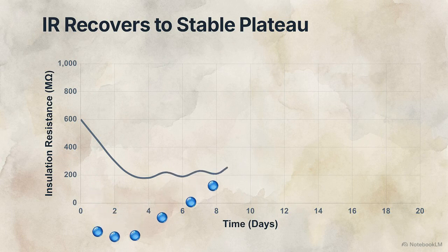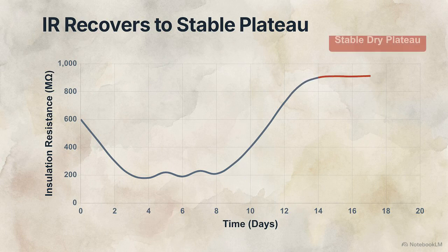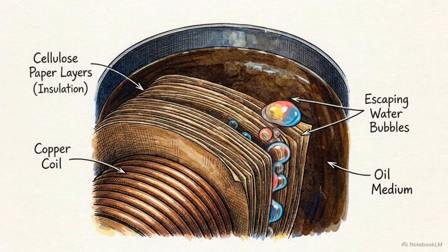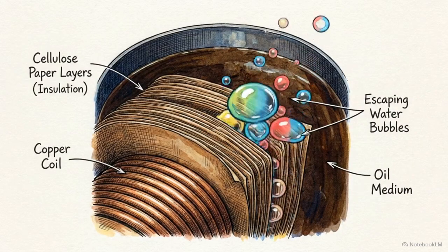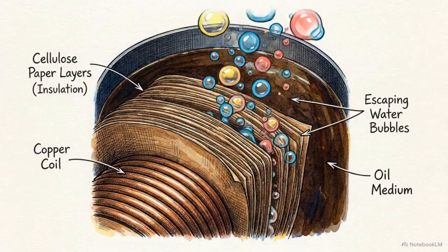Expect an initial drop in IR values. Heat actively pulls trapped moisture out of the paper and into the oil, lowering the resistance. As the vacuum extracts this moisture, IR values will stabilize and steadily climb into a high plateau. Following the curve rather than reacting to the initial drop confirms that the solid insulation is actually drying out.